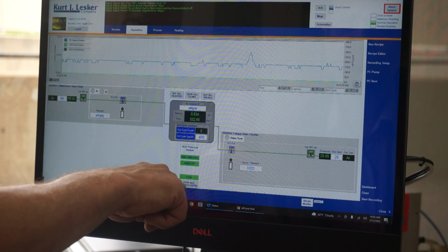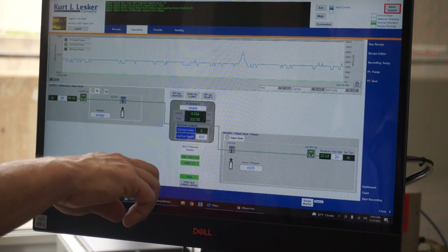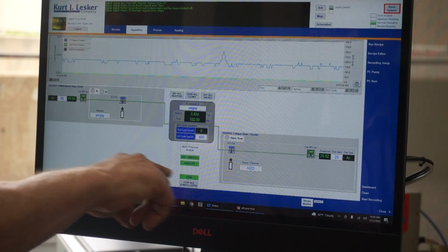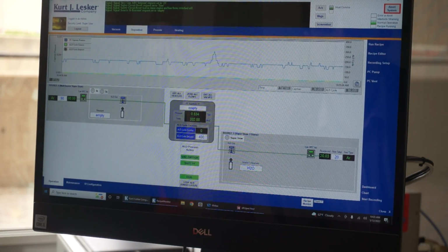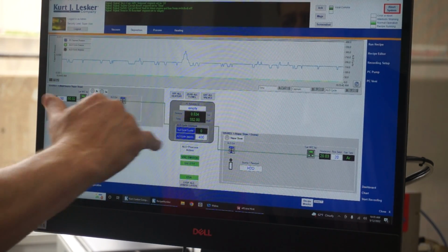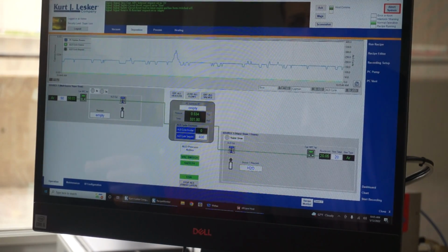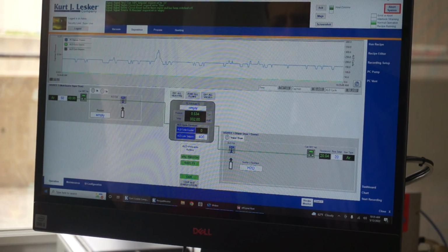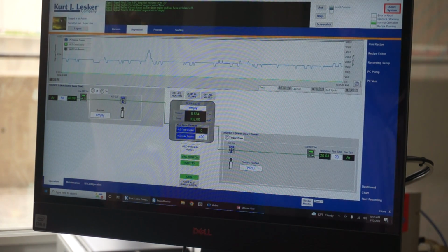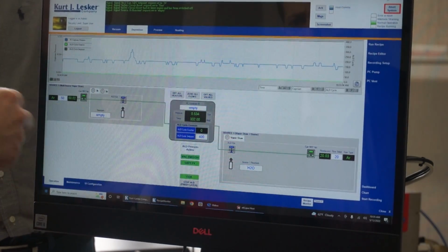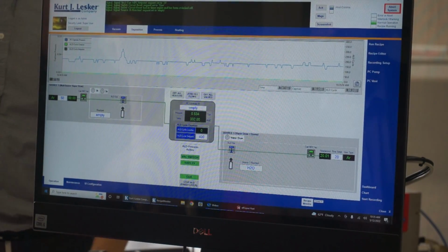Stop ALD layer is just a nice way, if you wanted to stop it before, you could hit stop ALD layer and it'll finish on that cycle. It'll allow the cycle to complete and then it'll stop. Or like yesterday, we were changing this to a smaller number. So if you have 400 cycles, and you're on cycle 200 of 400 and say, oh, I want to stop this, you could plug in 201 or 202.